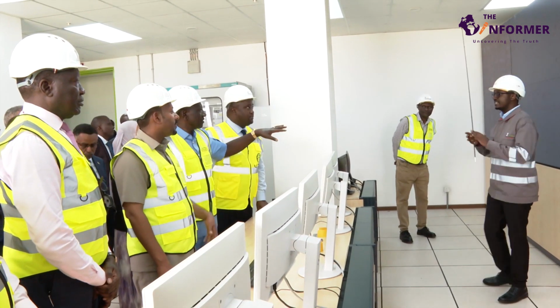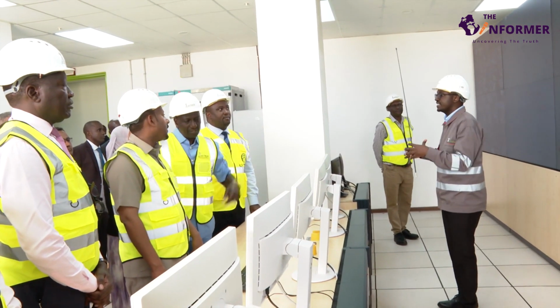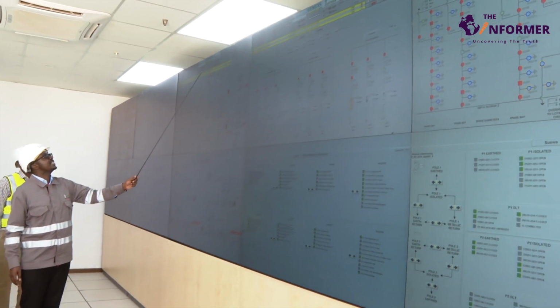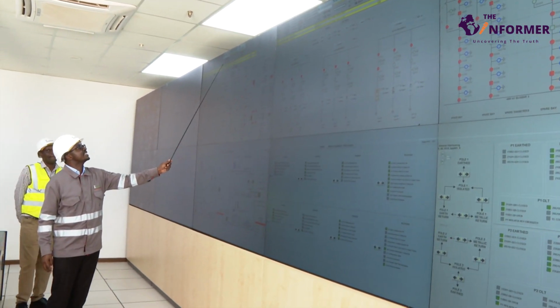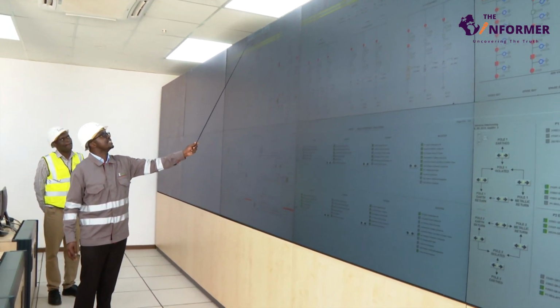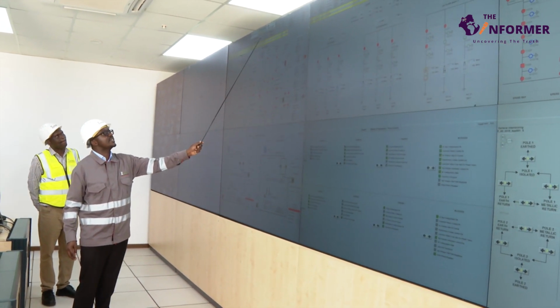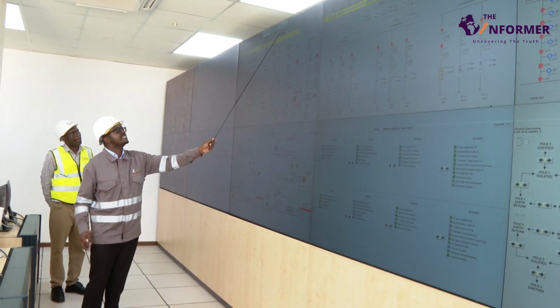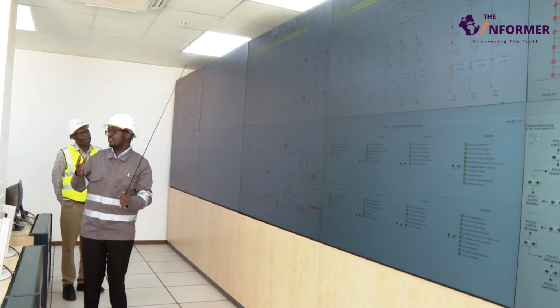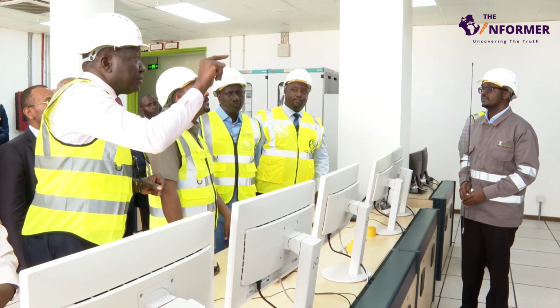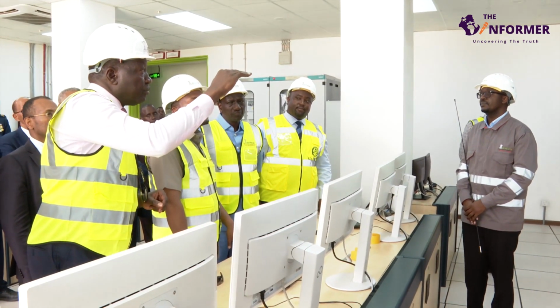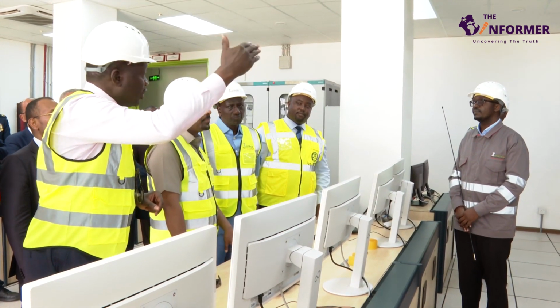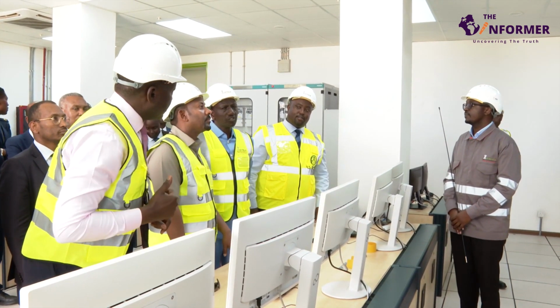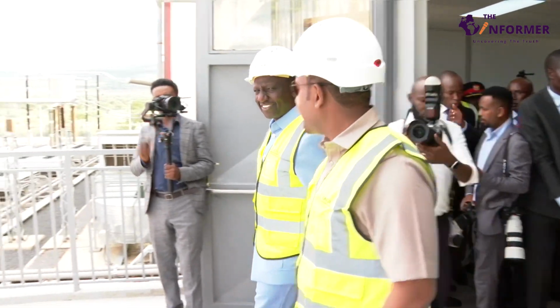This is just around here, from within. For example, you can see these are the current readings. Ethiopia is sending 200 megawatts and we're receiving 196 and 195, it varies. The 5 megawatts we are dropping because of losses, out of the 200, represents 2.5% of the losses.